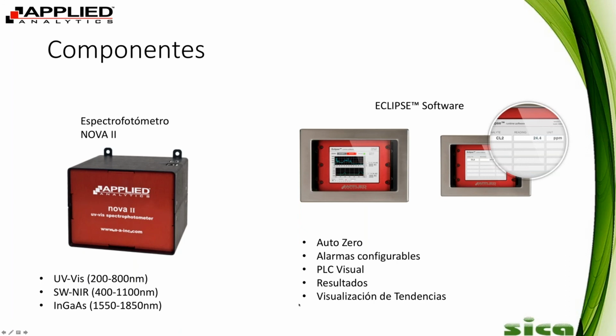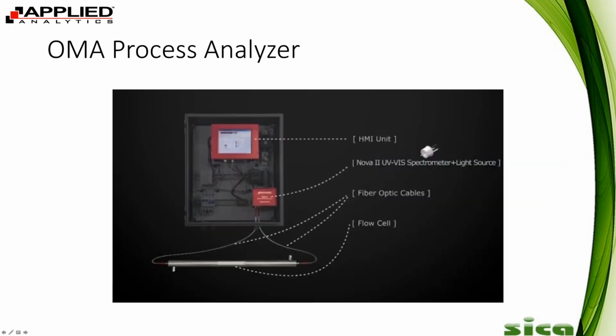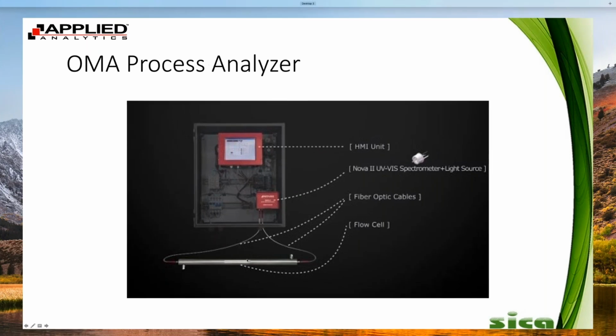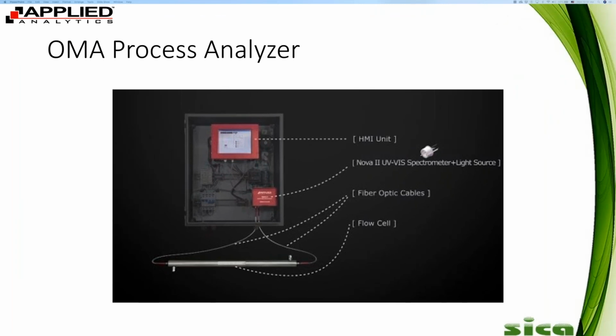So the spectrometer communicates with the HMI via Ethernet cable. The spectrometer is your detector, and your HMI is basically your way of seeing those values and what your detector is reading. Next. So here's a video, which I hope will work. Just talking about the OMA, which is our most customizable analyzer. It's what we use to measure if a chemical absorbs in the UV range, then we use the OMA and we customize the OMA or calibrate the OMA to measure the chemical that you want.